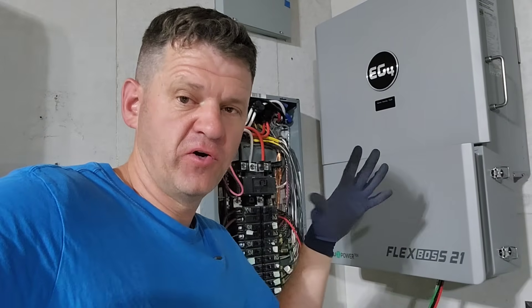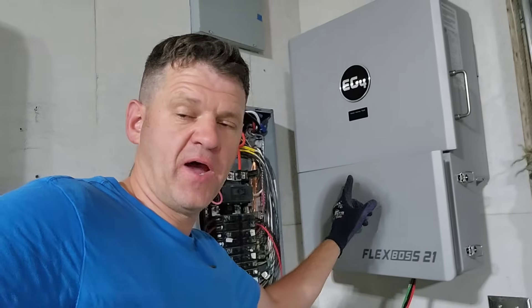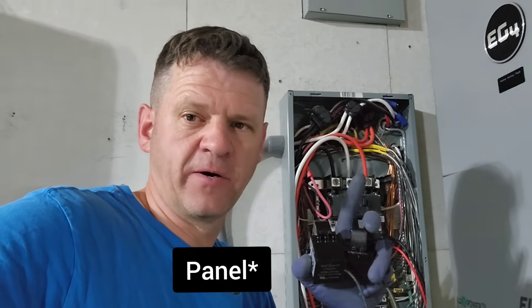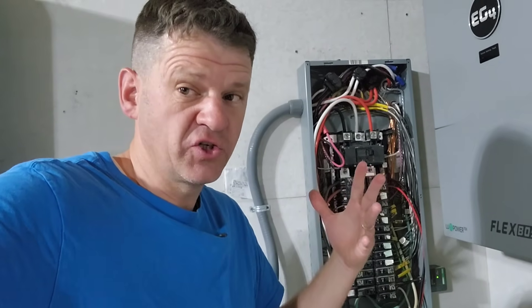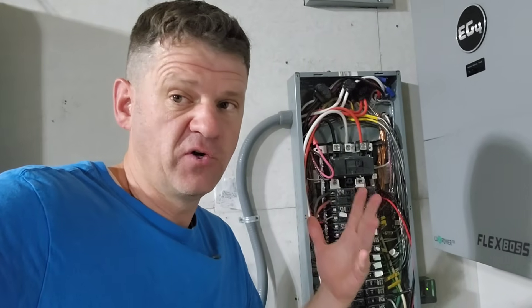The beauty of a hybrid inverter is that once I have solar connected, it can send power out the grid port and into my electrical panel. It will actually backfeed into the grid right now unless I use CTs — current transformers. I'm going to clip these right where my grid comes into my electrical meter, and that will ensure no power is going out to the grid. I tested this setup a few days ago and it's been running, so I know it works.